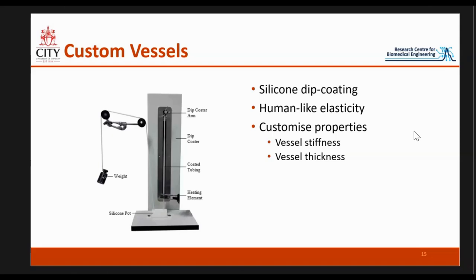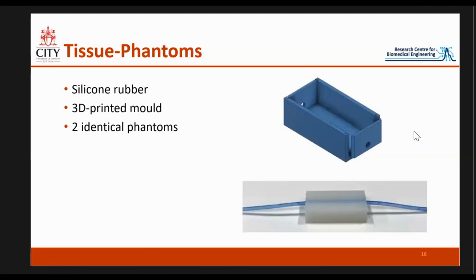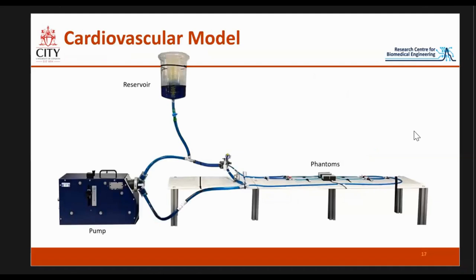We can customize the properties by adjusting the silicone mixture — depending on what additives we add, we can change the stiffness. We can also adjust the timing and heating to change the vessel thickness. We then need to put the vessel into a phantom. For this we use more silicone, this time in a mold — we put the vessel through, add silicone around it and allow it to cure. The goal was to create two identical phantoms with the same vessel and tissue mixture, and attach them to the system.